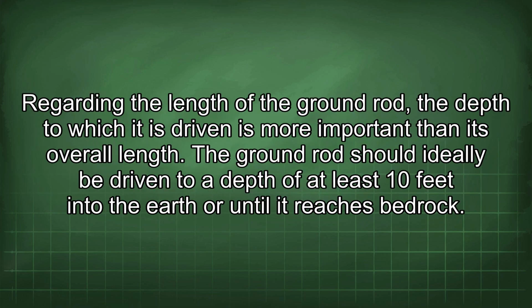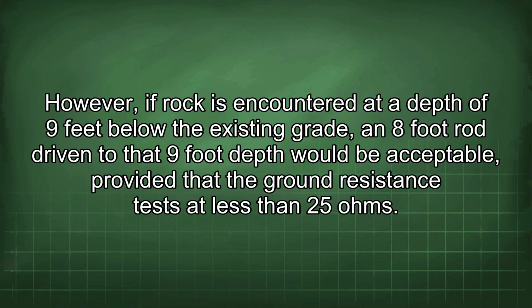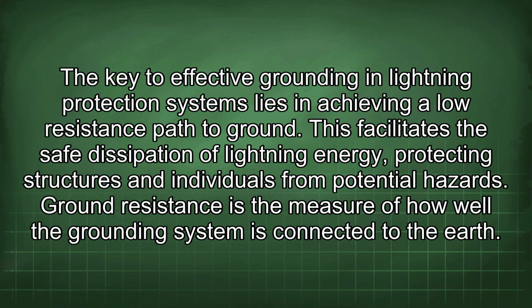Regarding the length of the ground rod, the depth to which it is driven is more important than its overall length. The ground rod should ideally be driven to a depth of at least 10 feet into the earth or until it reaches bedrock. However, if rock is encountered at a depth of 9 feet below the existing grade, an 8-foot rod driven to that 9-foot depth would be acceptable, provided that the ground resistance tests at less than 25 ohms. The key to effective grounding in lightning protection systems lies in achieving a low resistance path to ground.